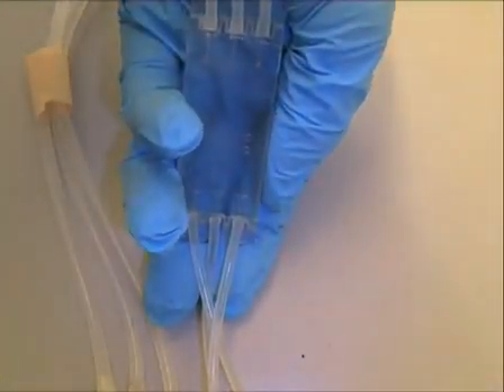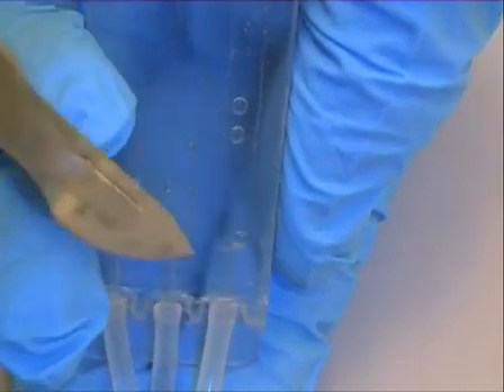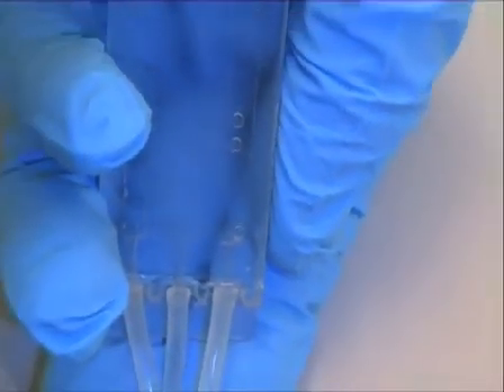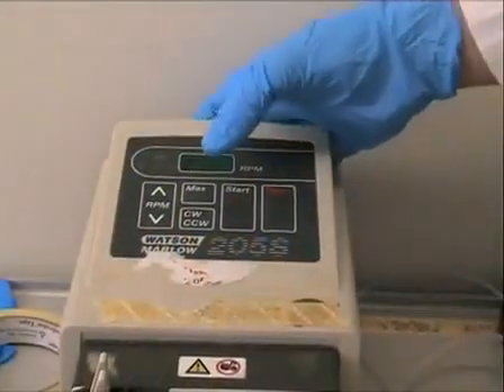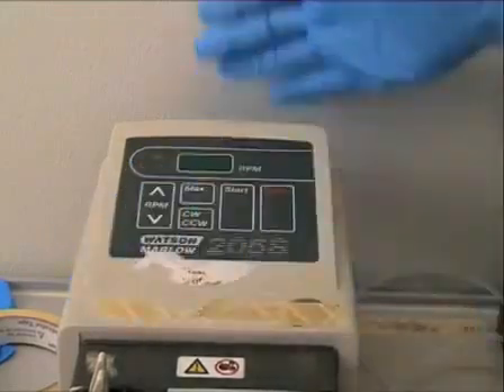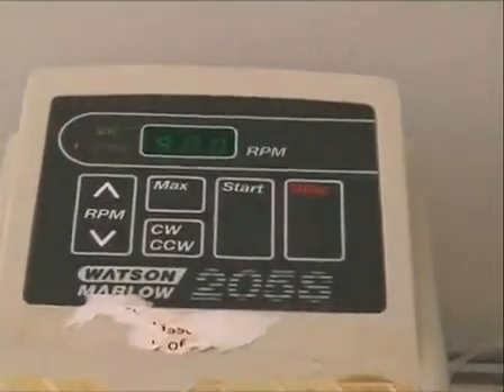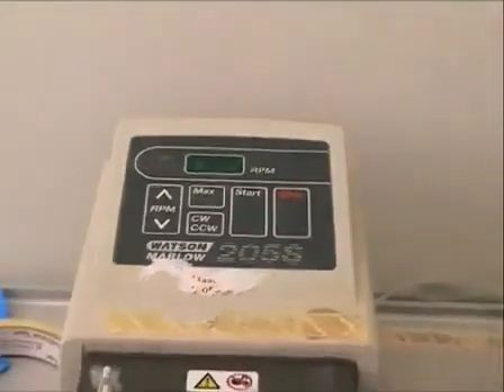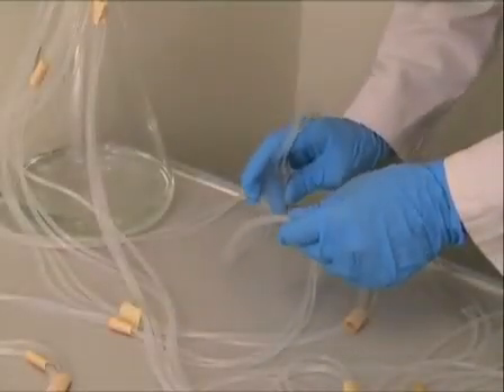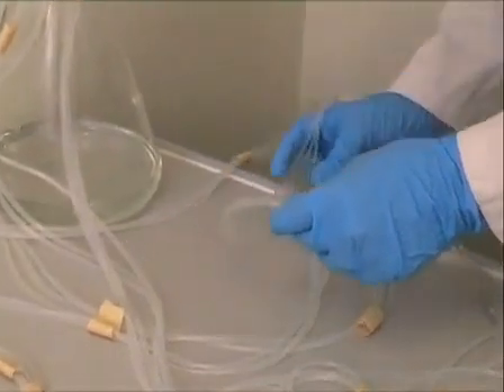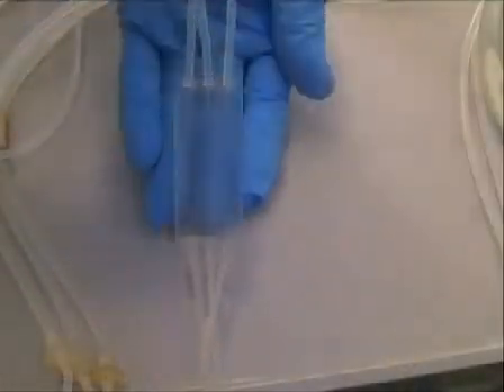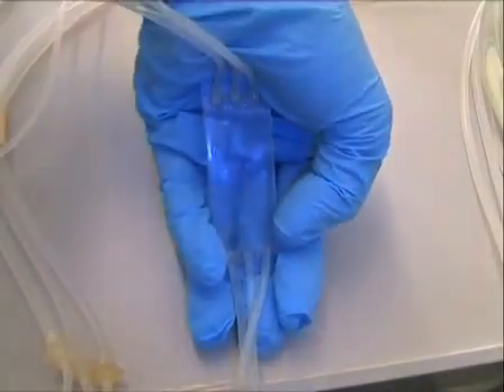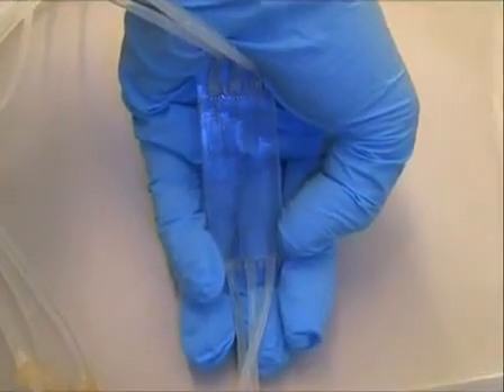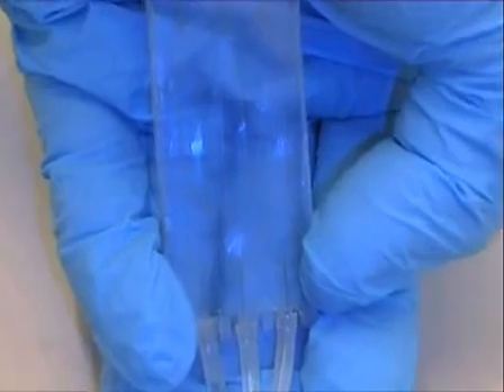An important step in the sterilization of the system is the removal of bubbles from the flow cells. Such bubbles can easily be seen in the flow cells shown here. For the high success of bubble removal, turn the pump to its highest rounds per minute. This will lead to a higher liquid flow in the flow cells, which in time will help to get rid of the bubbles. Lift the flow cell and lift the tubings leading to the flow cell, and firmly tap the flow cell on the table to loosen the bubbles in order to get them flushed out with the liquid flow. This procedure will sometimes take a long time, but you will in this way be able to get rid of the bubbles if you are patient.